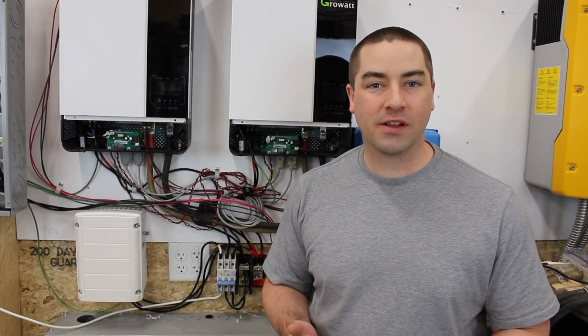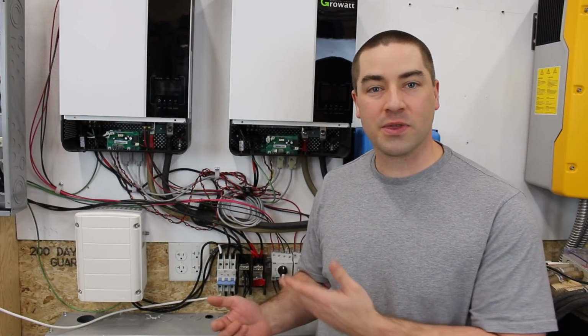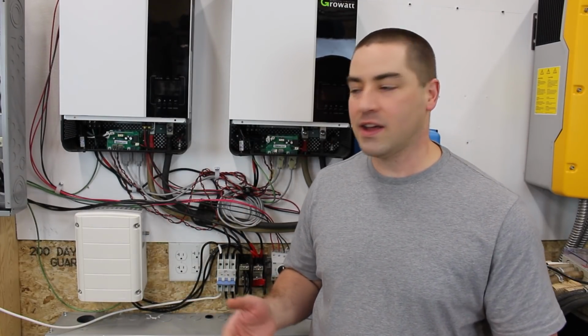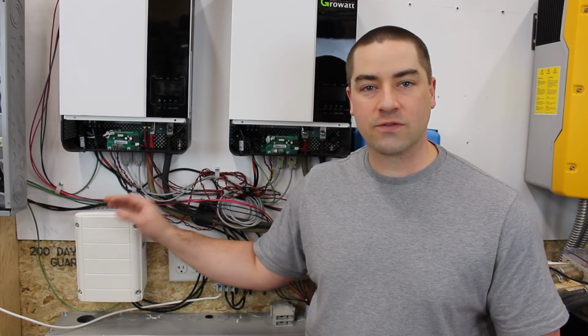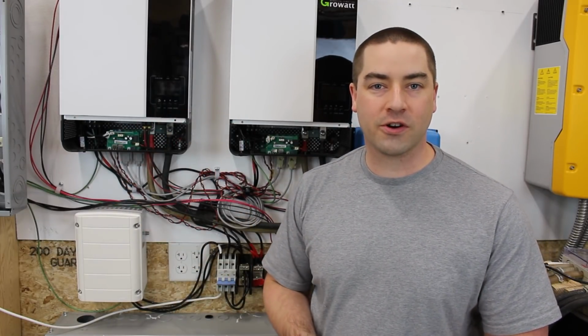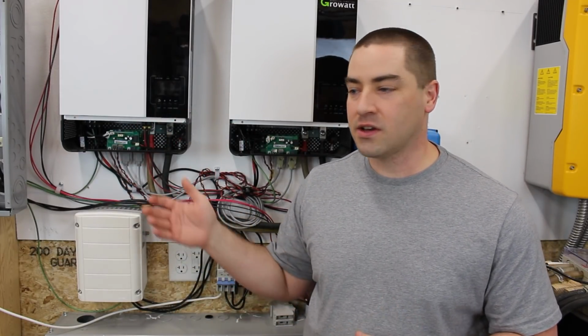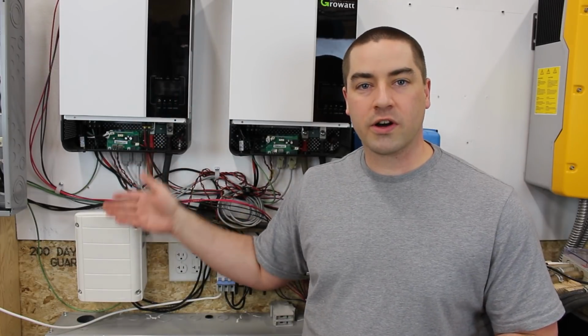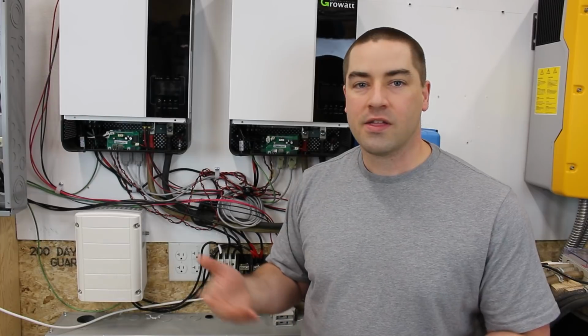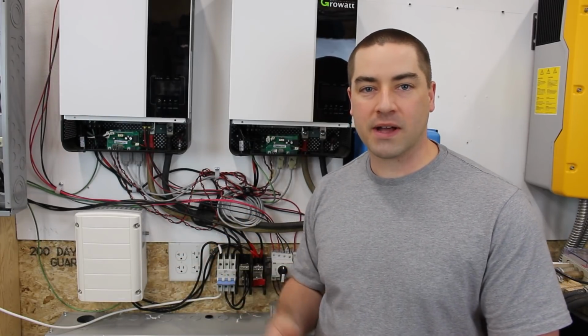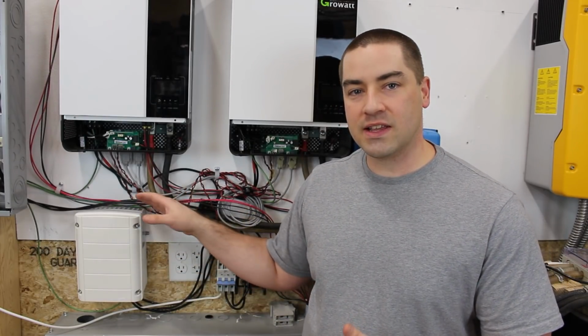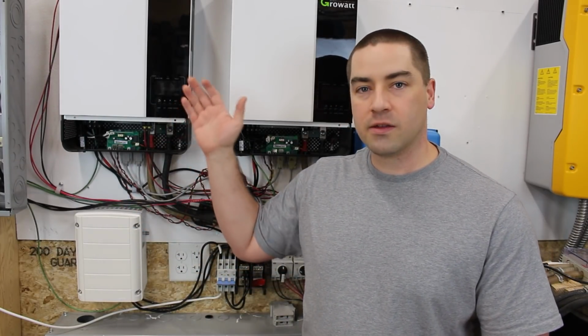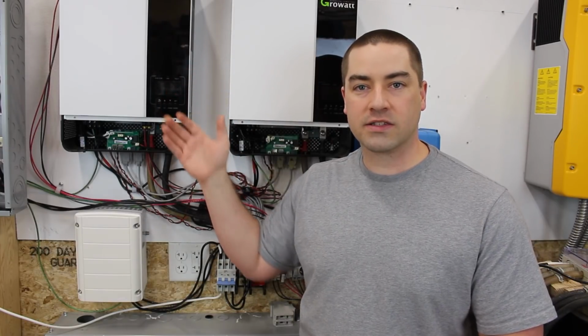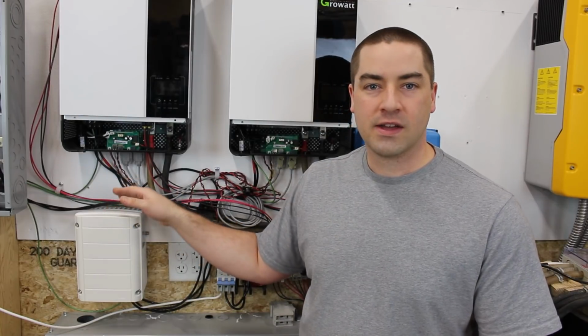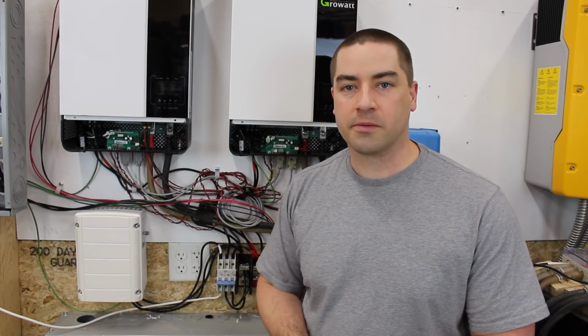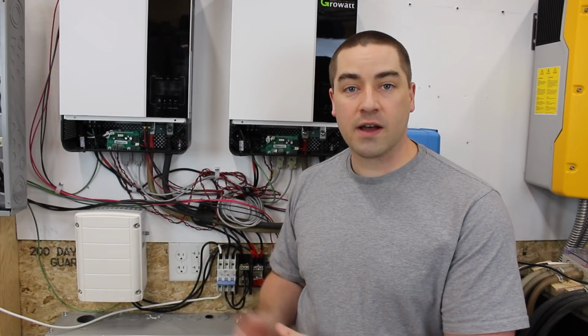Well, there it is, you guys. I'd love to hear from all of you in the comments below if you think this is a good idea or not, if you're using one auto transformer with 2 or more inverters. Now again, if I was using a 1-to-1 ratio of one auto transformer to one inverter, then I wouldn't worry so much about this. But this is just in the situation that I have where the potential is 10 kilowatts of inverting power to 5 kVA of auto transformer. So I think it's a viable solution.